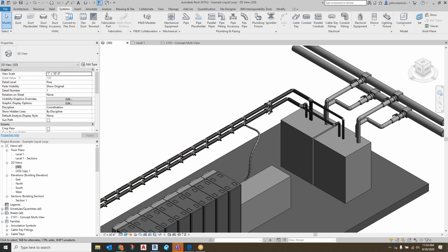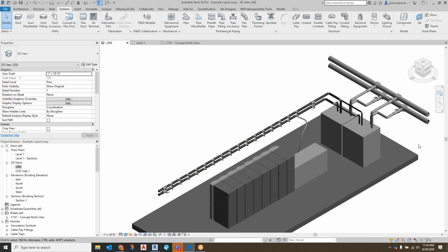That's exactly what I was thinking - we just pick a number, be it 400 or 800, a nominal number, recognizing that in most cases no one's going to hit that number exactly. If I choose 800, someone else might go with 1 meg. But conceptually, they're going to have to use slightly bigger pipes, a slightly bigger CDU, slightly more of this.